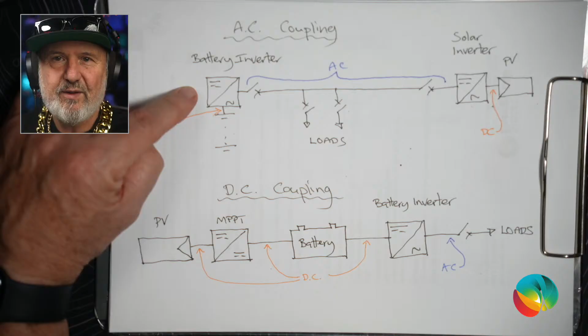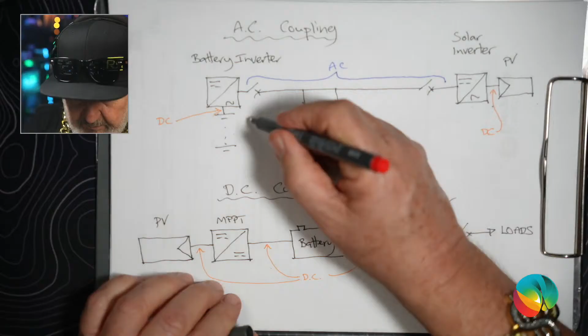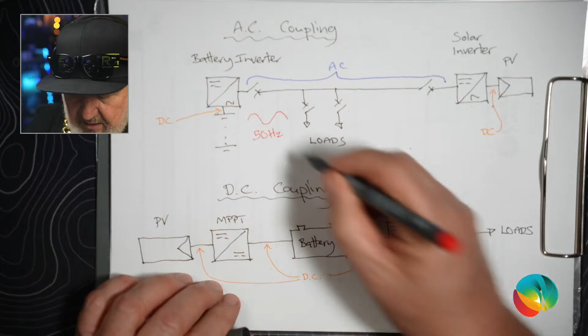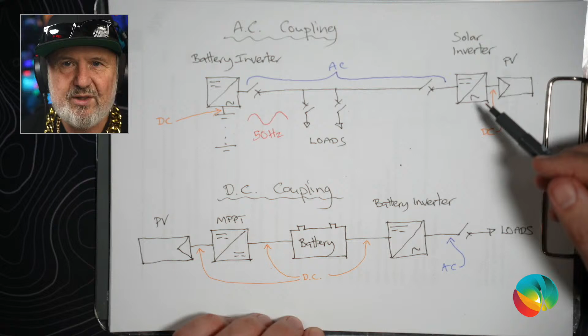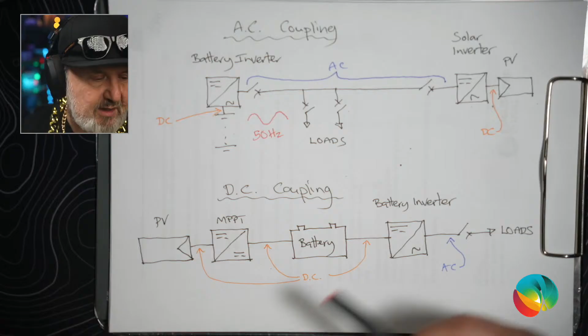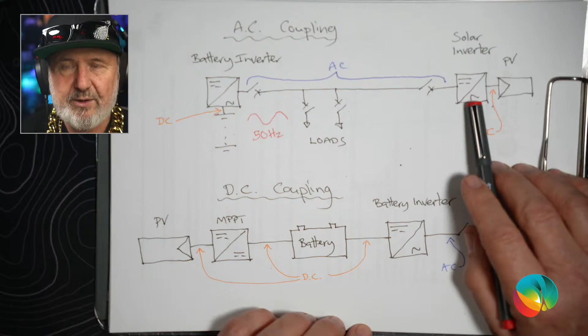Well, for a start, the battery inverter is what we call the grid forming inverter. It creates a stable 50 hertz sine wave. So coming out of here, we've got a sine wave like this. There's our 50 hertz sine wave. And the solar inverter actually doesn't connect to it instantly. It sits and monitors the AC network, and it watches the frequency. So it's watching the frequency, and it can change its internal frequency before it parallels.